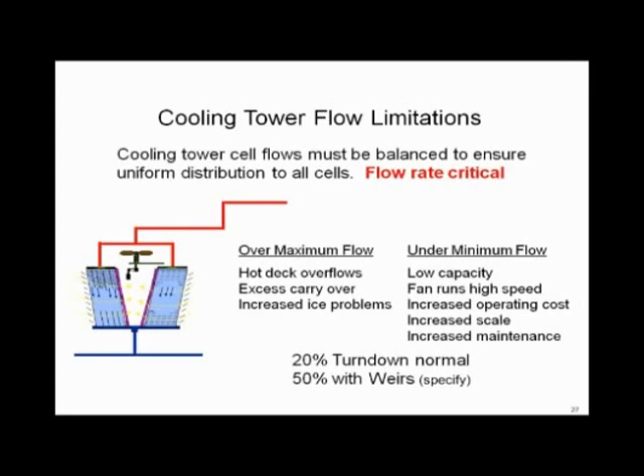Until recently, most towers — unless you specified otherwise — would only turn down 20 to 25 percent. For example, if a tower's design flow is 1,500 GPM, a 20% turn down means the minimum allowable flow would be 1,200 GPM. With 50% turn down, that minimum drops to 750 GPM. Get below that minimum and the towers don't work correctly — you start having issues.